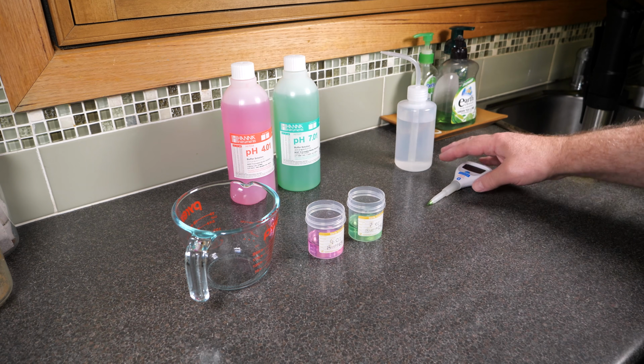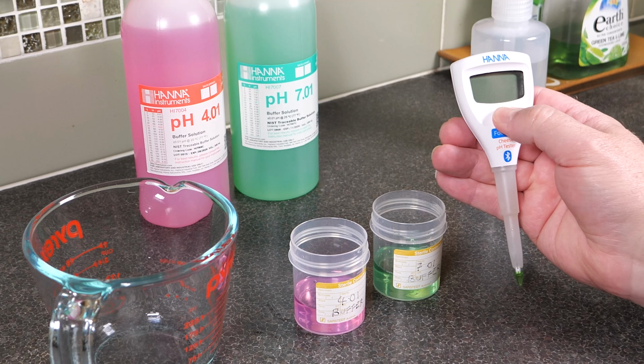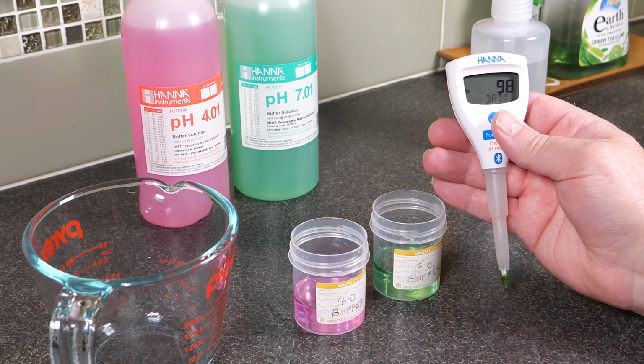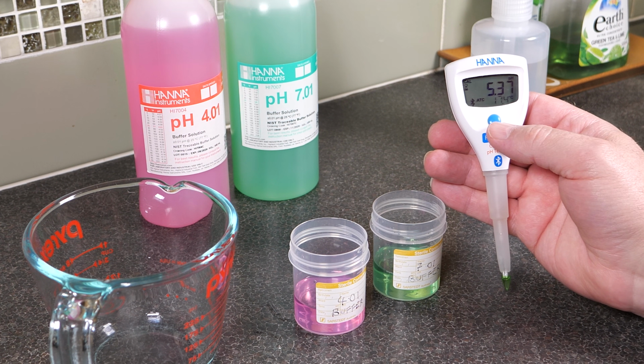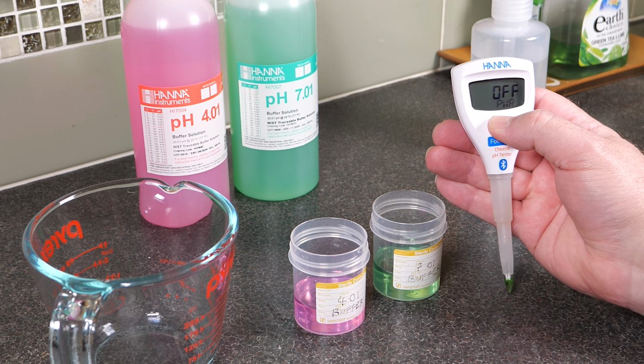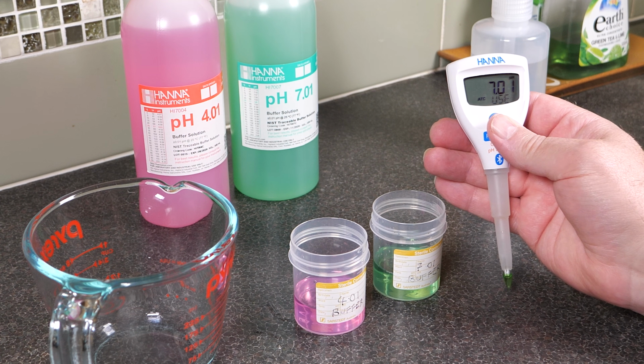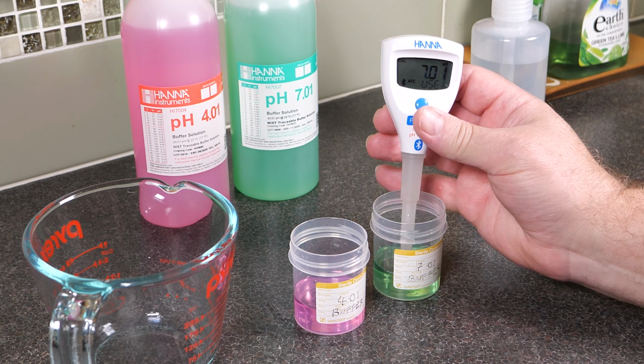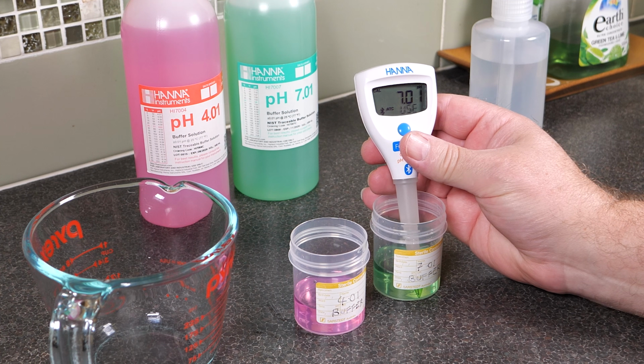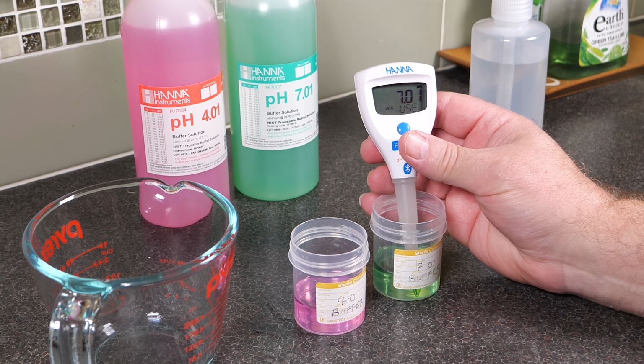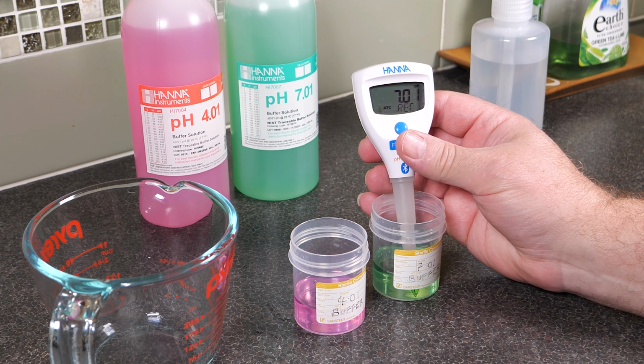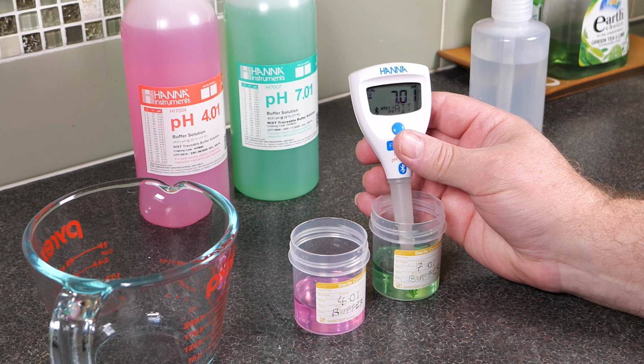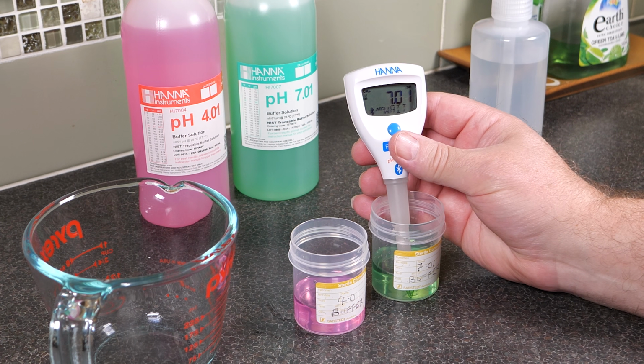Now, calibration of this meter is so easy. You turn it on. Wait until it says what the battery is and comes up with a reading, and then you hold it down. It pretends to power off, but then it goes into calibration mode. And then it tells you to put it into the 7.01. Then it detects it. There you go, it's figured out that it's in that one. And it tells you to wait until it's calibrated. So when the hourglass stops flashing, it'll go to the next one.